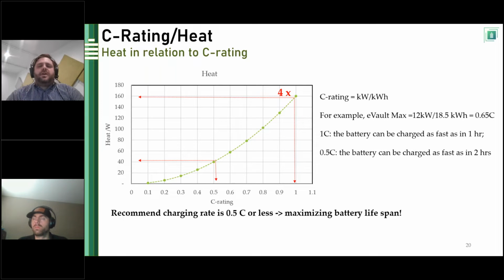Well, maybe you want to take a look at your programmable settings and make sure that the full capability of the Sol-Ark is there for power outages, but with regard to charging the battery or even selling back to the grid via discharge, if it makes sense to sell back or charge at a slower rate, those clients who really like to fine-tune their systems will see a battery that lasts beyond the product warranty if they dial the system back a little. Again, it's a site-specific choice. Some customers want to use the full capability. Other customers really want to fine-tune for longevity.